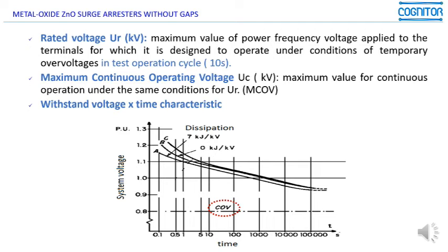And on the other side, if one atmospheric pulse is arriving with a very short duration, these values of voltage are much higher than the ones of the temporary overvoltage. Then the surge arrestor, also in this case, should support these values of overvoltage without discharging, or discharging above a certain specified value.